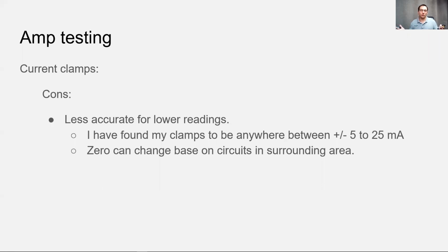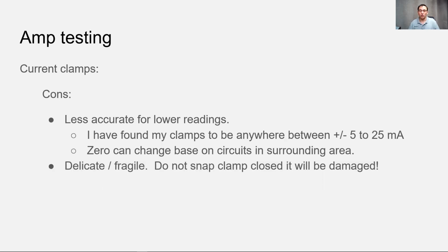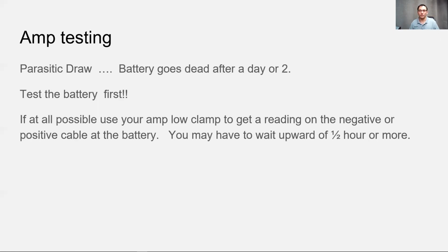In my experience, I usually see anywhere plus or minus 25 milliamps on the amp clamps that I use, and that's good enough to get me in the ballpark for what I'm doing, especially even for a low amp draw. Another drawback of these things is they're delicate and fragile, okay, so don't try to snap it closed, it will be damaged.